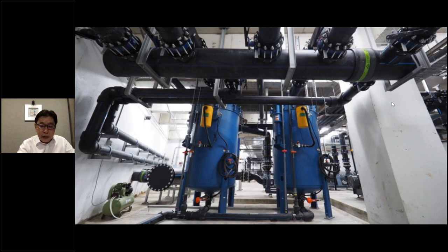Another tricky issue is the rinse. If you cannot handle the rinse, you will have problems. On top of changing the media and handling the valves, sometimes the valves couldn't close properly, so they will bypass the filter. Or maybe some of them can go to waste. You're wasting a lot of chlorinated water. So there are a lot of issues.